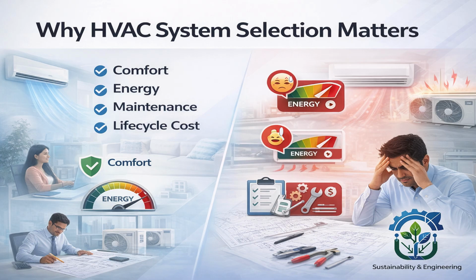Most HVAC problems do not come from poor installation. They come from wrong system selections. If you select the wrong system, energy bills increase, comfort complaints start, maintenance becomes a headache, and the client loses trust. If you select the right system, the building runs smoothly for 20 years, maintenance is predictable, and energy consumption stays under control. This is why HVAC system selection is a consultant's responsibility, not a contractor's preference.